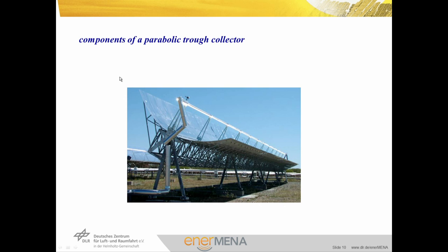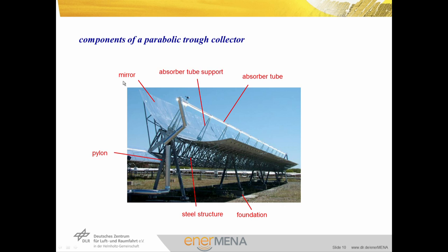The collector has the following components: foundation, pylon, steel structure, mirrors, absorber tubes, absorber tube supports, a drive, a tracking sensor, and a flexible tube. This flexible tube is necessary because when the collector is moving, the absorber tube part also moves but the connection piping system is still fixed. So between those two points we need a flexible tube. Before explaining the components in more detail, I would like to assemble a parabolic trough collector together with you.